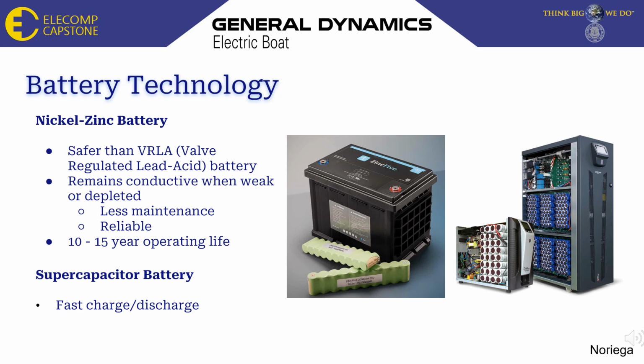Battery technology is important in the data center as they store emergency power in case power fails. Nickel zinc batteries are promising as they are safer than the standard lead acid battery, and typically have a longer operating life of up to 15 years. Another benefit is that they remain conductive even when depleted or weak, which results in increased reliability and less maintenance need overall.